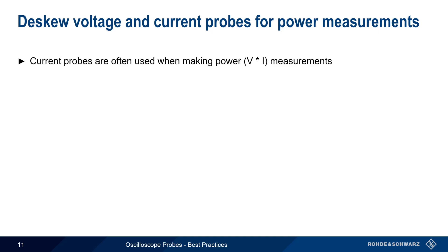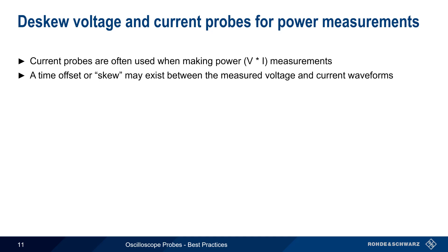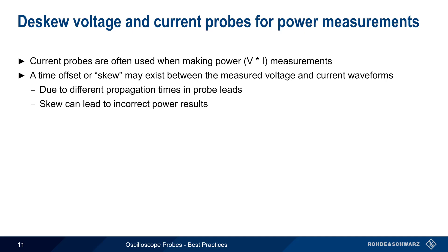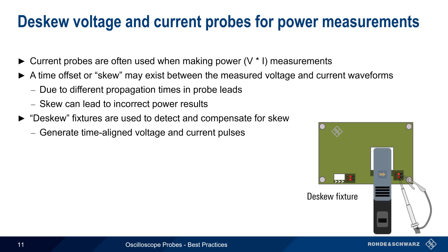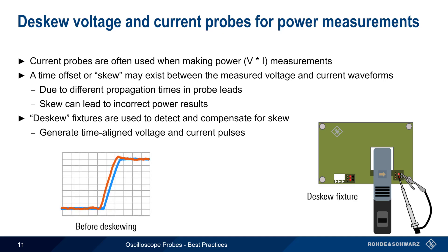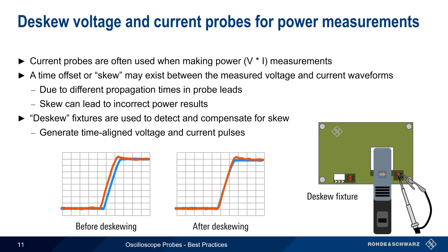Current probes are often used together with voltage probes when making power measurements, since power measurements require simultaneous measurement of both voltage and current. In some cases, a time offset or skew may exist between the measured voltage and current waveforms due to different propagation times in the probe leads, and this skew can lead to incorrect power results. Special de-skew fixtures are used to detect and compensate for skew by generating time-aligned voltage and current pulses. If these test waveforms are skewed, an appropriate de-skew or time offset value can be entered on the scope to bring the current and voltage waveforms back into phase and improve the accuracy of power measurements.